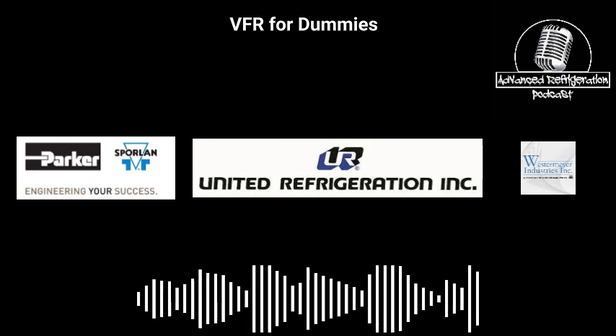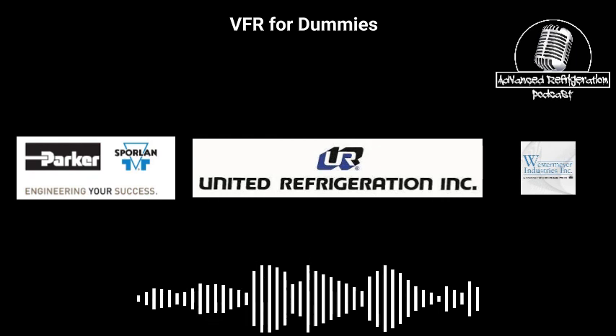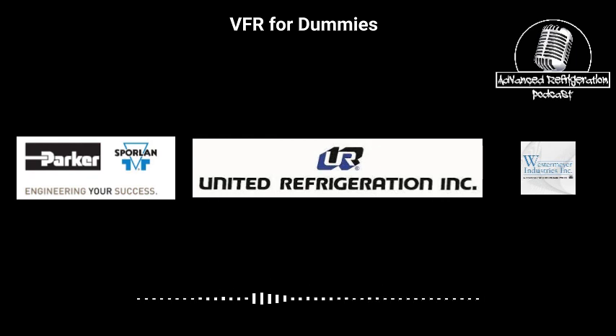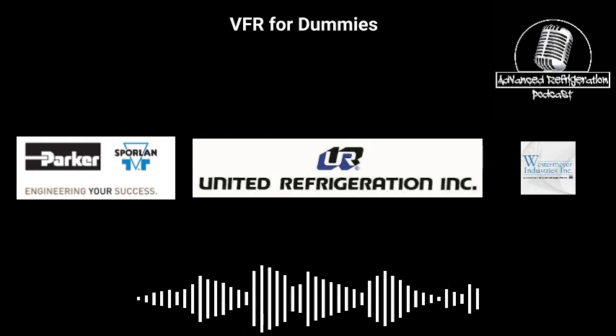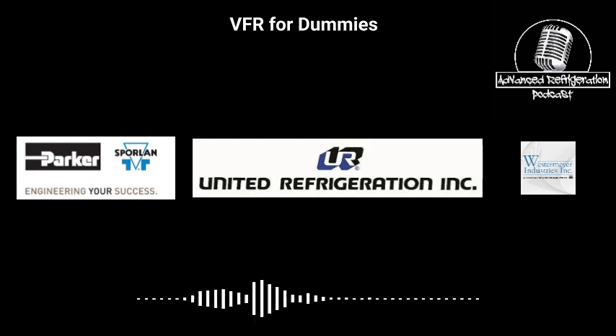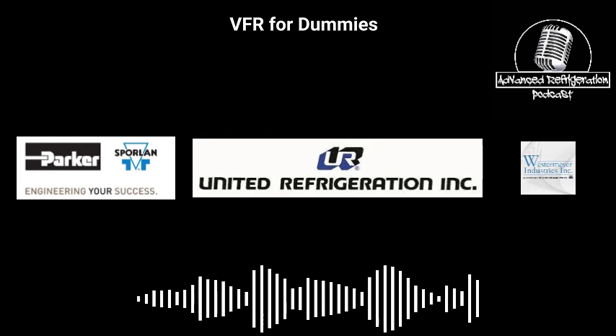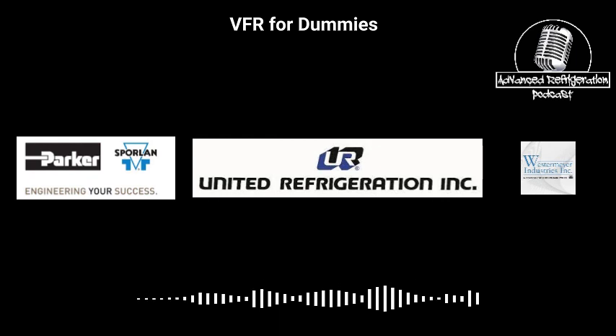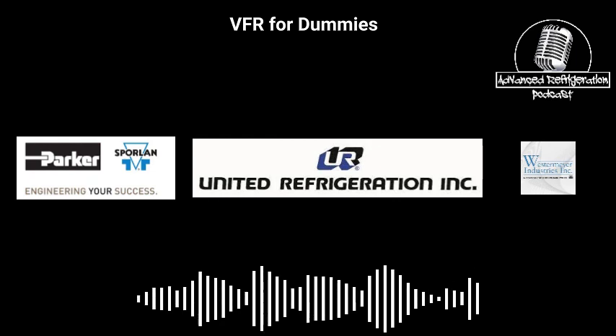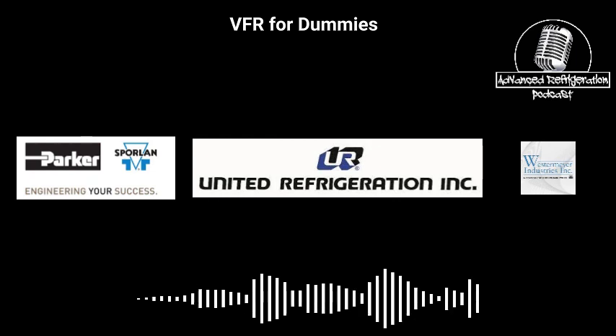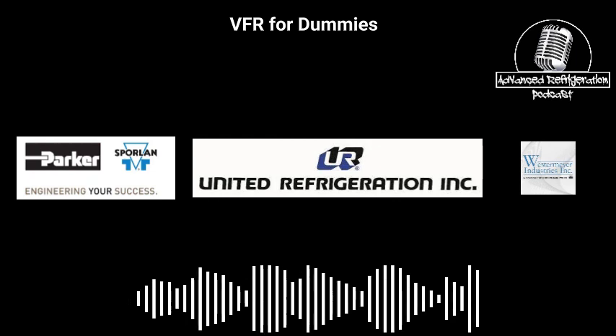So that's the big difference between a conventional air conditioning system and a VRF system: what component is doing what. My background is primarily in Daikin, but all VRF is the same concept. We have a condenser or an outdoor unit located outside the building, or it could be in the building if we've got a water cooled unit. We can think of that as the central plant. From there, we use the compressor to send refrigerant around the building or bring it back.